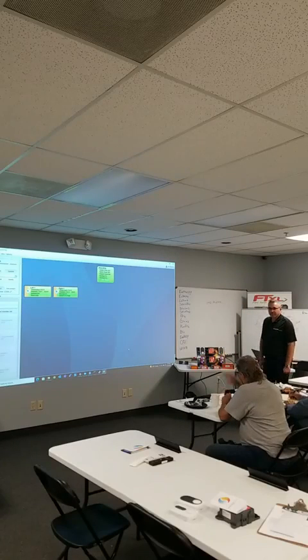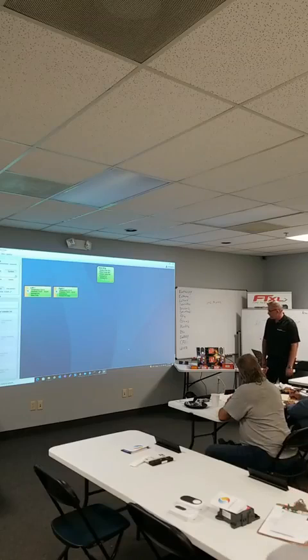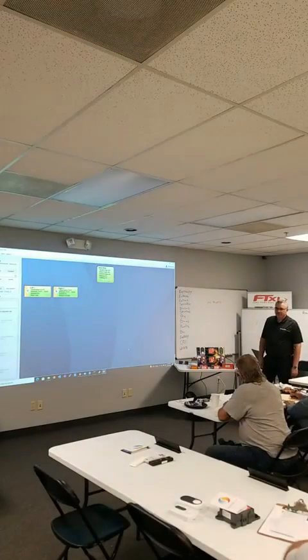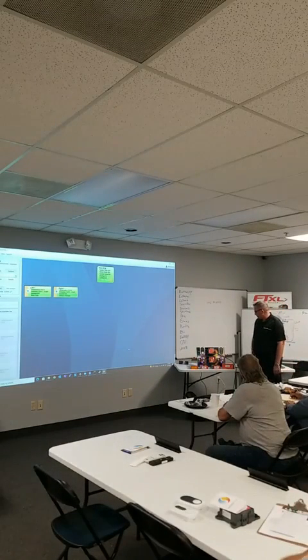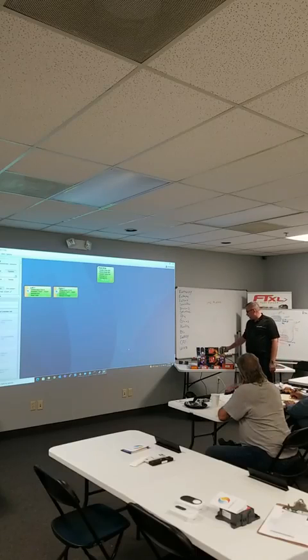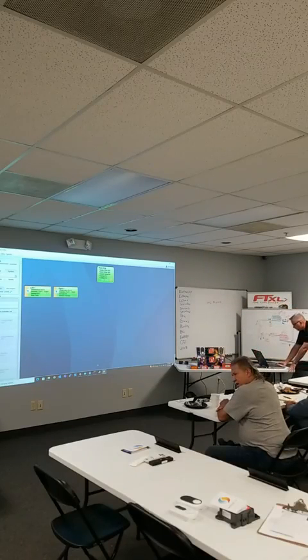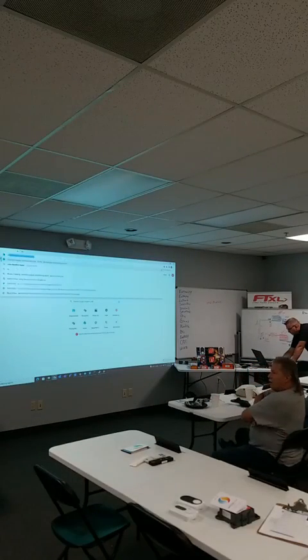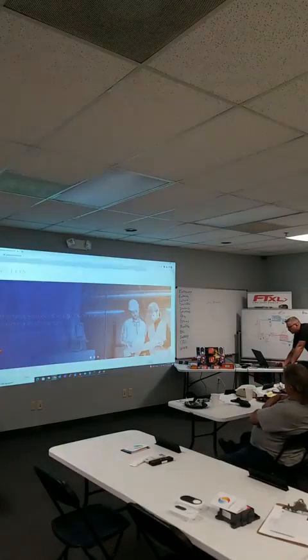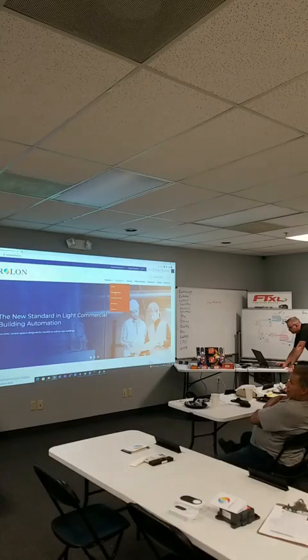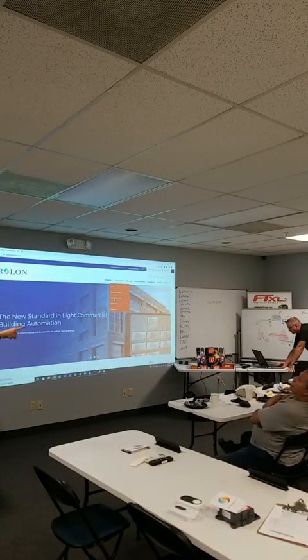You install sensors everywhere — do you remember, one wire back there? You have to wire this, you essentially wire the sensors to the controller, and then the controllers wire between one another. Most of the time the zone dampers are spread out throughout the space, so a single twisted pair could connect the two together. The wall sensor would get wired, and those VAVs are all daisy-chained together with a 2-wire pair.